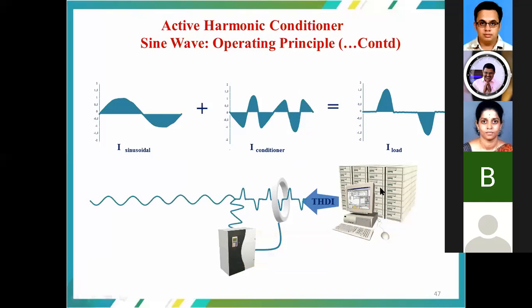So the THDI is going to get injected from the system, that is from the nonlinear load, which is going to affect the sinusoidal component. So this is going to be the conditioner unit. So the I conditioner is going to get injected into the system. Thereby the current drawn by the load is going to be sinusoidal. So if every load connected to the system is going to draw the pure sinusoidal component, which is not going to affect the system voltage waveform or the current waveform, means the system voltage or current shape is going to be maintained as pure sinusoidal. Thereby we are going to have the increased efficiency as well as the better operation.